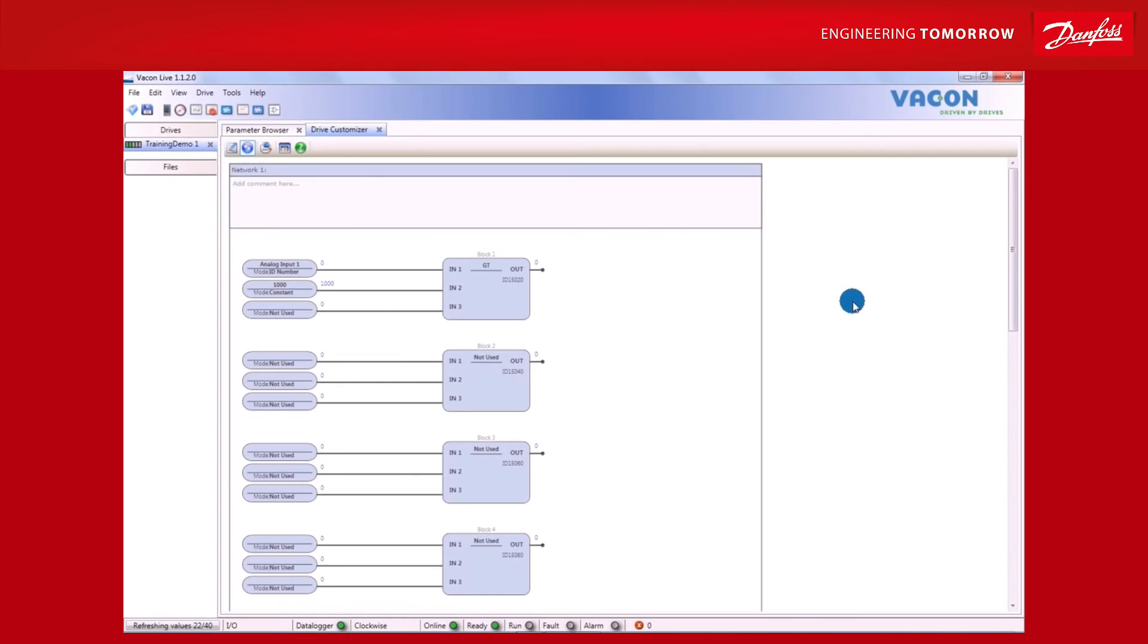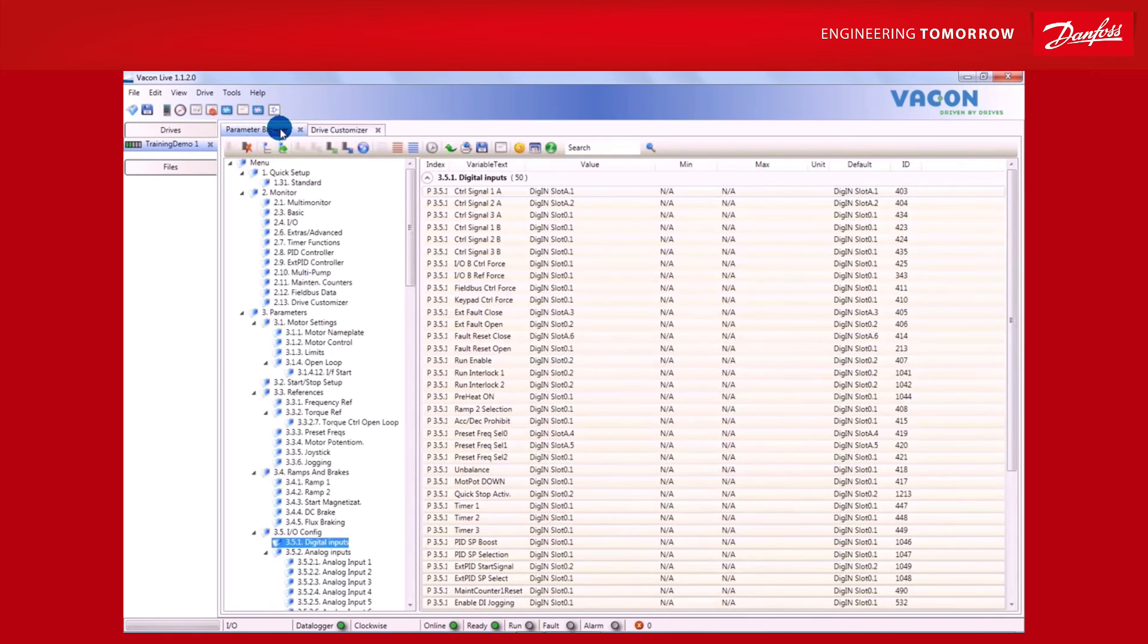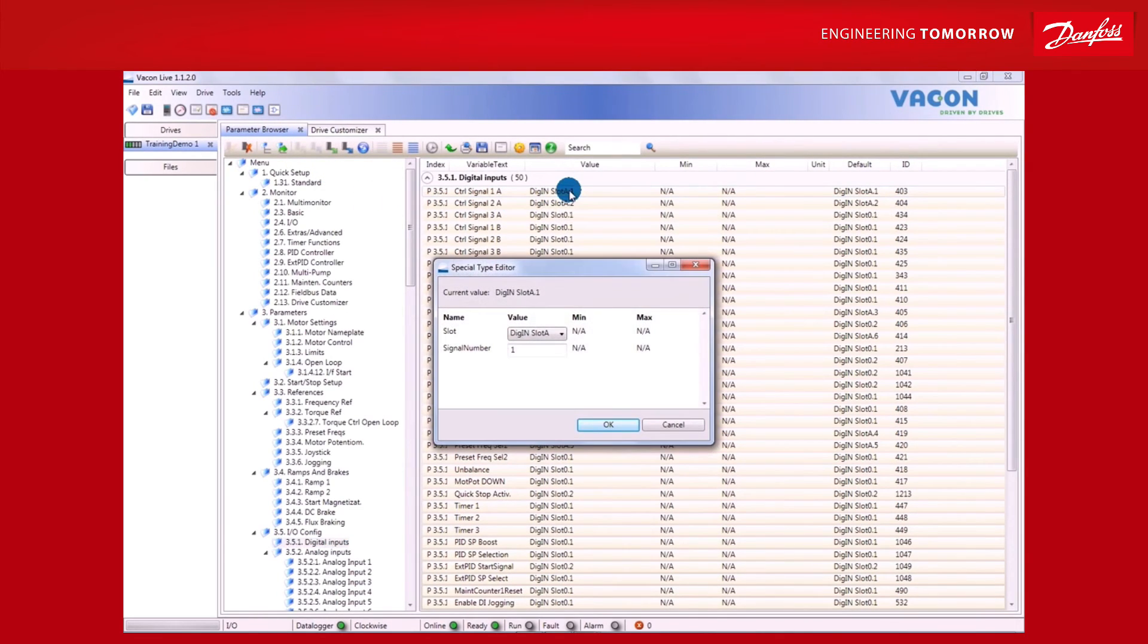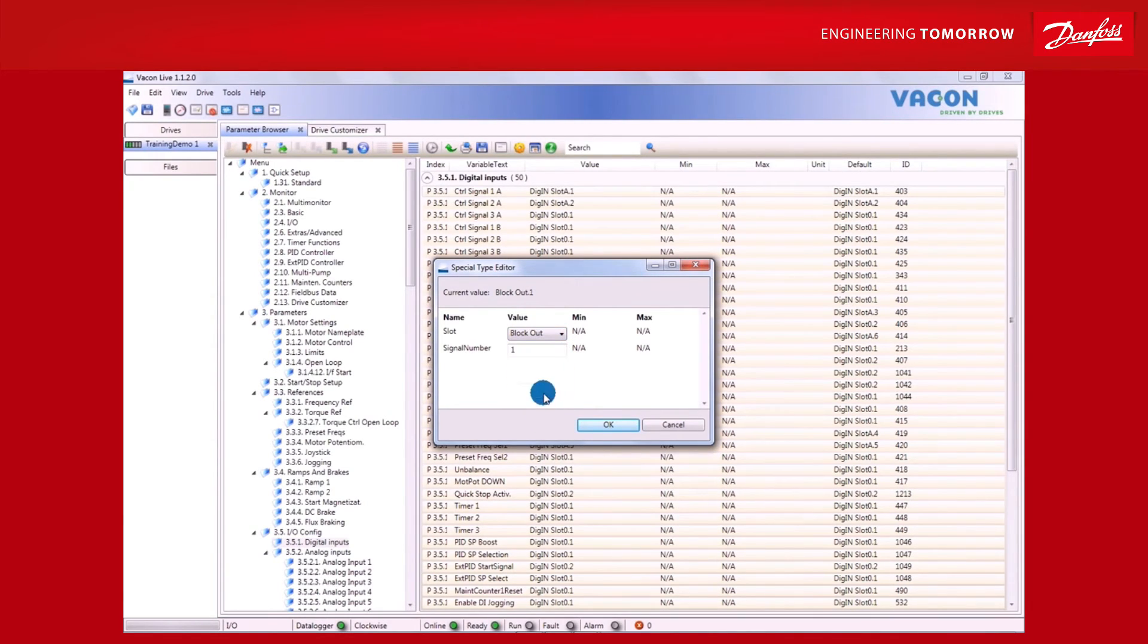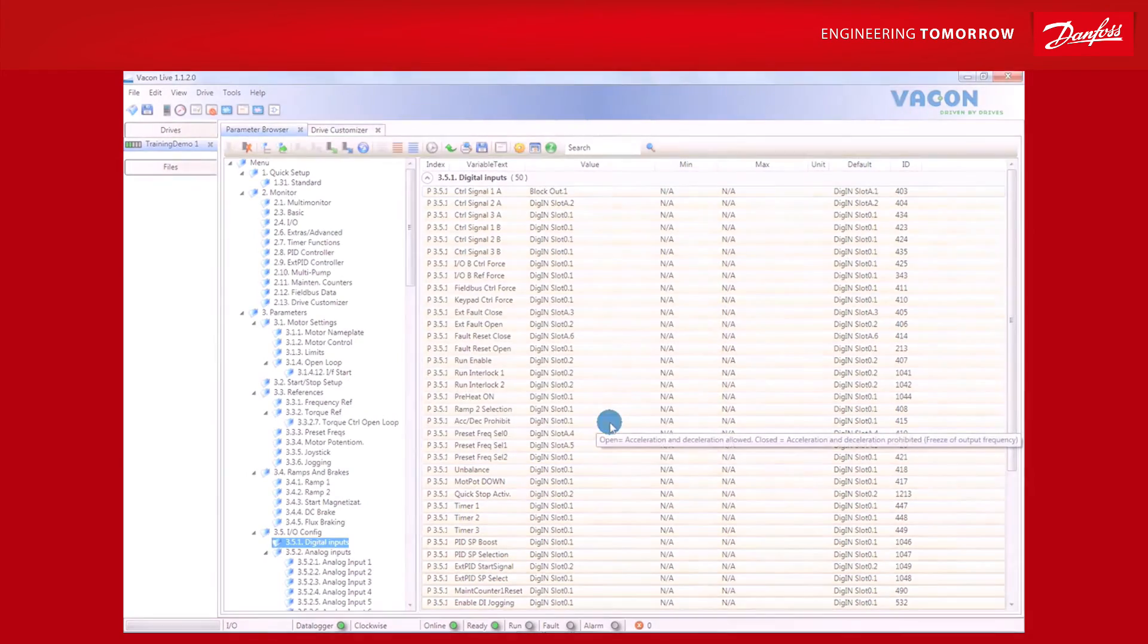The drive is still inactive, since the signal hasn't been given to the start command. Activating the drive can be done from the parameter browser window in the list of digital input options. By selecting control signal 1A, the start command is selected in slot 1A. This is now the first digital input on the control board, and will be designated as block output for block number 1.